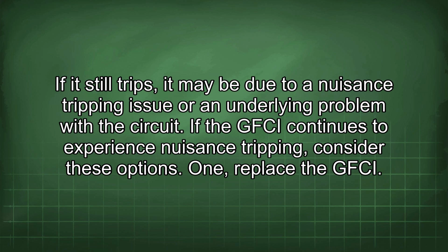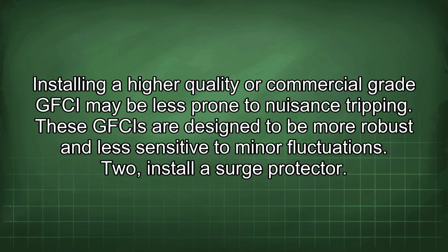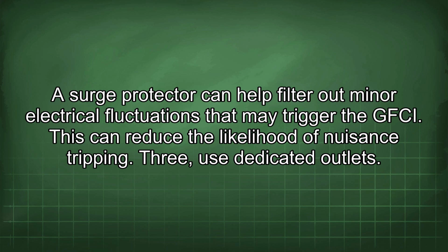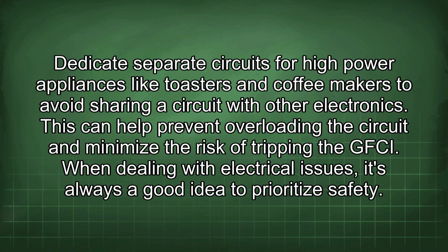If the GFCI continues to experience nuisance tripping, consider these options. 1. Replace the GFCI. Installing a high-quality or commercial-grade GFCI may be less prone to nuisance tripping. These GFCIs are designed to be more robust and less sensitive to minor fluctuations. 2. Install a surge protector. A surge protector can help filter out minor electrical fluctuations that may trigger the GFCI. This can reduce the likelihood of nuisance tripping. 3. Use dedicated outlets. Dedicate separate circuits for high-power appliances like toasters and coffee makers to avoid sharing a circuit with other electronics. This can help prevent overloading the circuit and minimize the risk of tripping the GFCI.